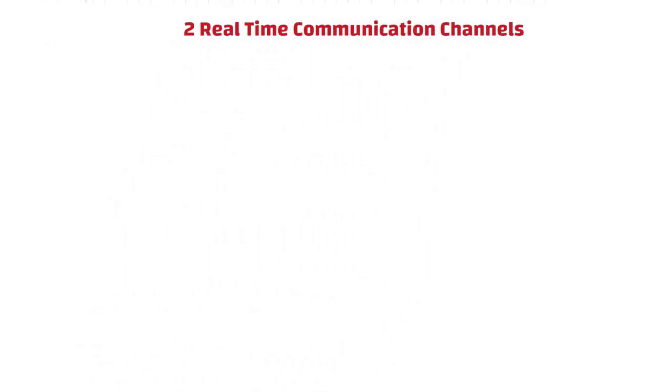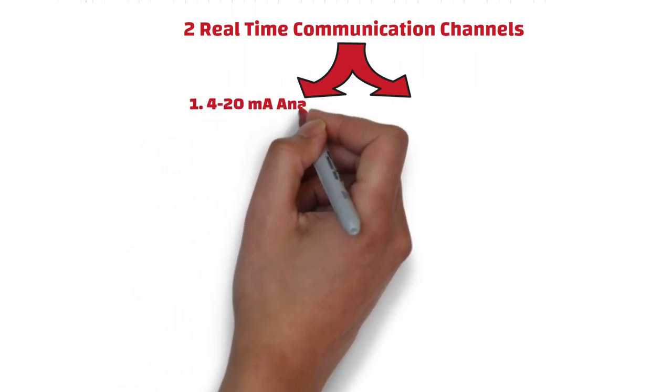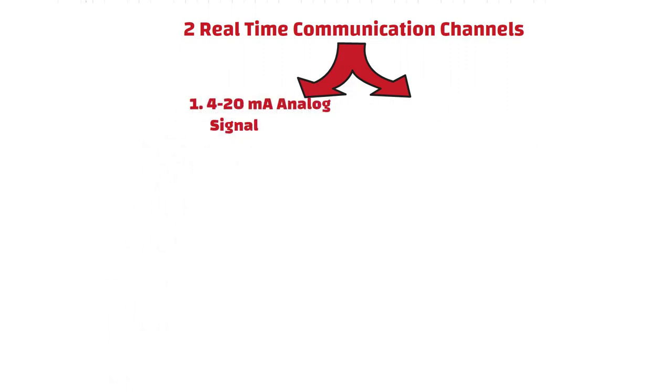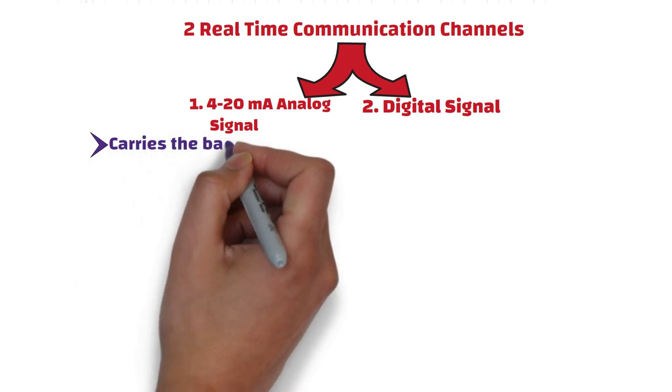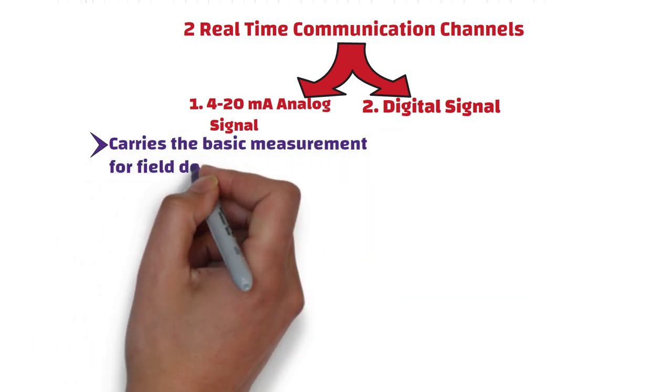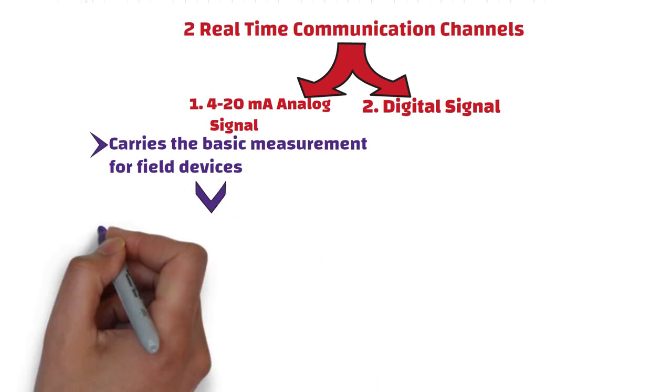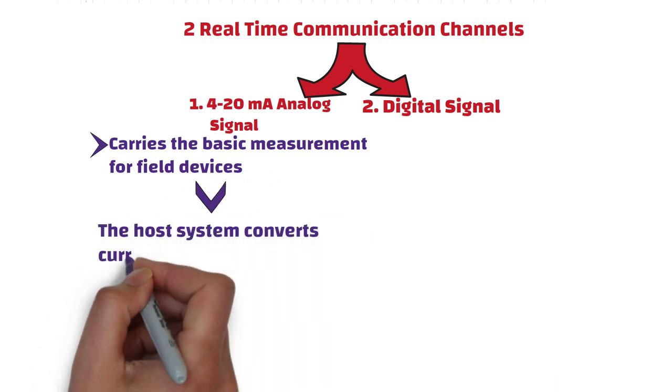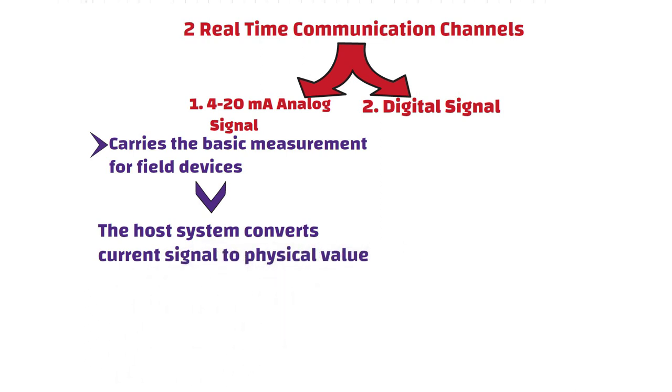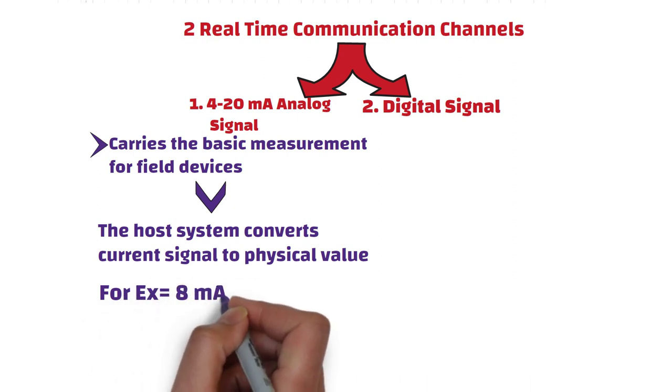Furthermore, HART provides two real-time communication channels. One channel is for 4-20 mA analog signal. Another channel is for digital signal. The 4-20 mA signal carries the basic measurement for field devices using the industry standard 4-20 mA current loop. And the host system converts current signal to physical value according to parameters defined by HART software. For example, host device converts 8 mA output of field device to 20 liters per second.